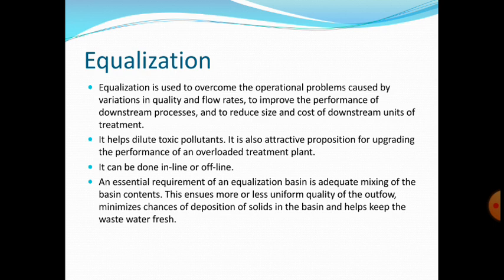Equalization is the process of controlling hydraulic velocity or flow rate through a wastewater treatment system. It prevents short-term high volumes or flow surges from forcing solids and organic material out of the treatment process. The influent to an industrial wastewater treatment plant varies in flow and concentration of pollutants because discharges from manufacturing processes are not constant. Equalization is used to overcome operational problems caused by variations in quality and flow rates, to improve the performance of downstream processes, and to reduce the size and cost of downstream treatment units.